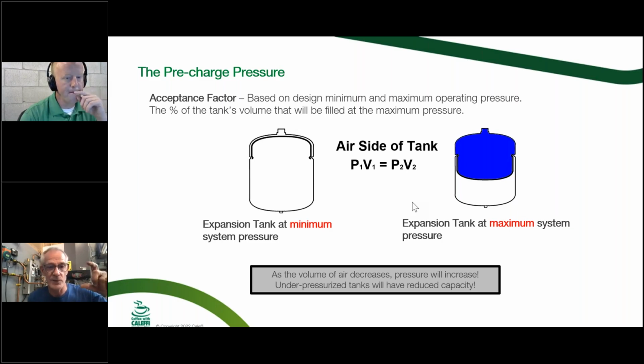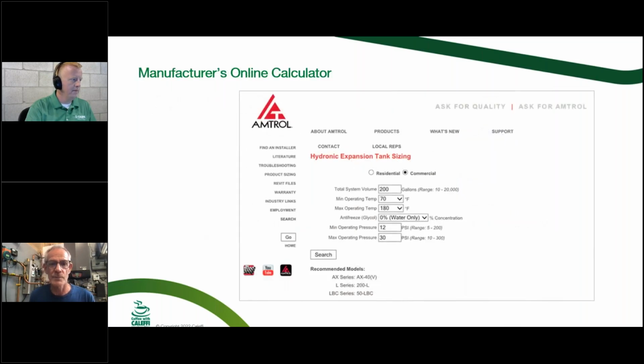And I think Wiesman calls that a safety seal. You got a little bit of water, so if there's a condition in your system where the pressure could drop below what you filled it at the day you filled it, you got a little bit of fluid in there, so your gauge is not going to drop to 0. If you got a leak in your system, you start flipping out because your gauge went down to 0. And where that's going to happen, and the slide will be coming up, is a solar thermal system. But since this is coming up next.